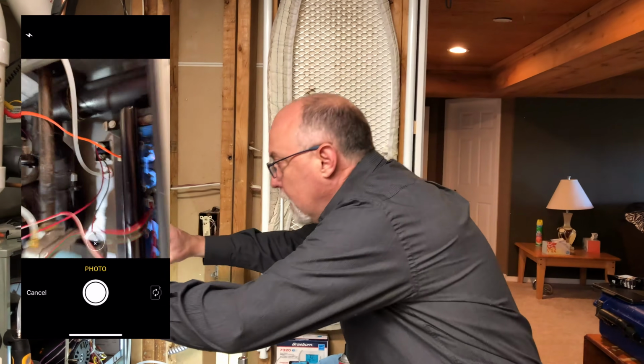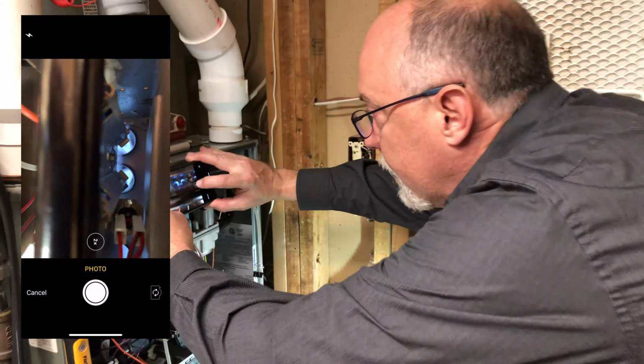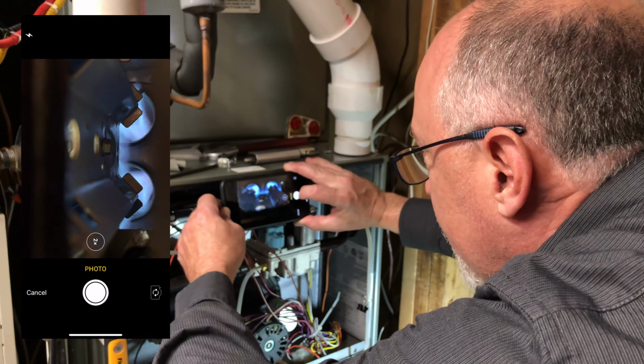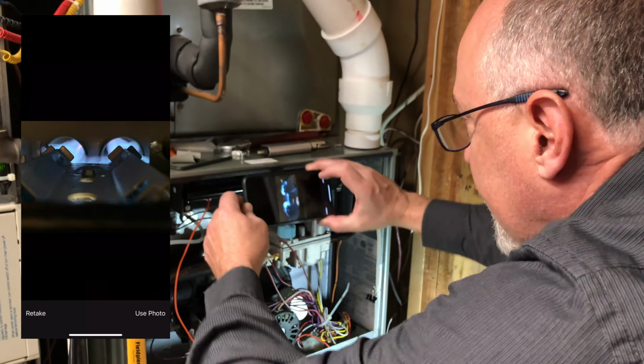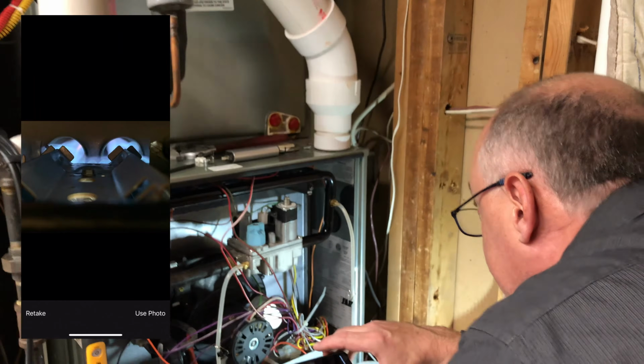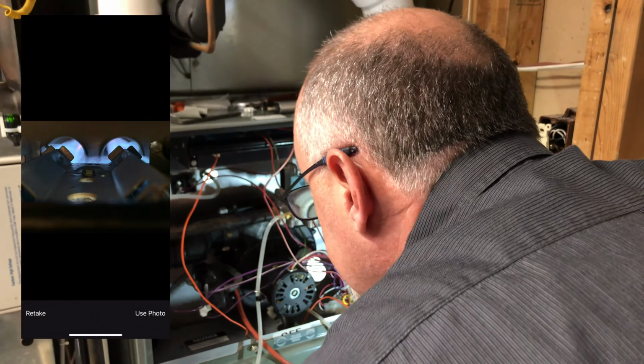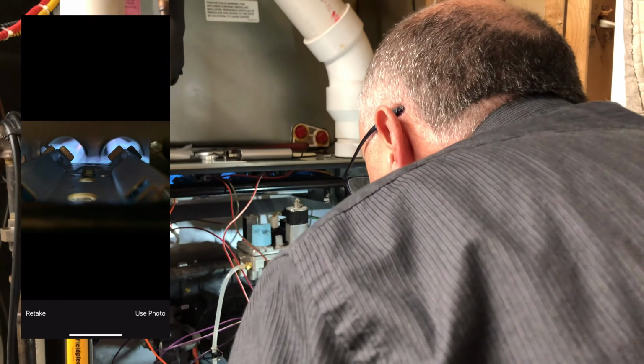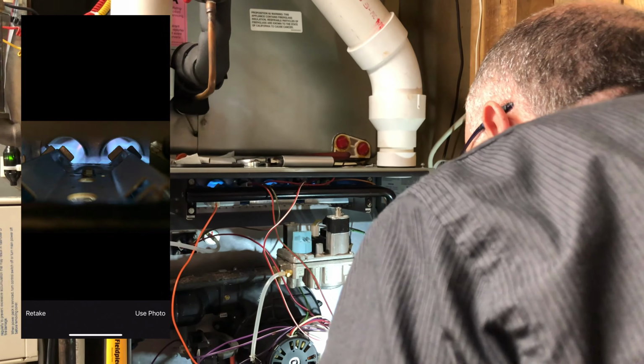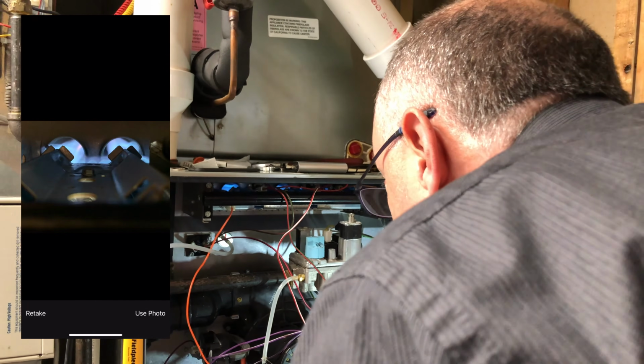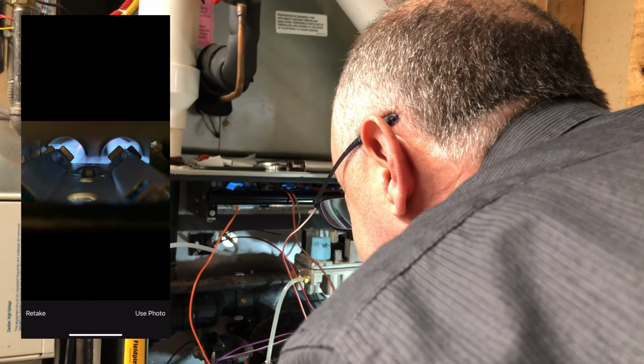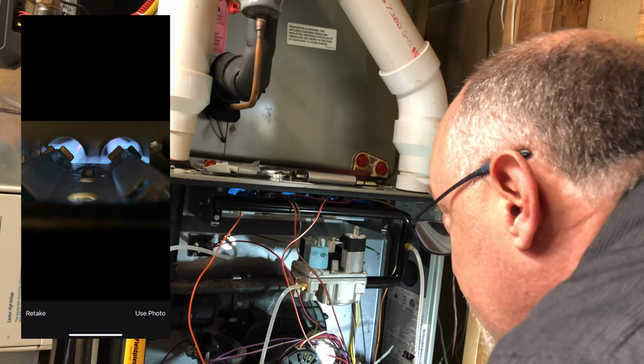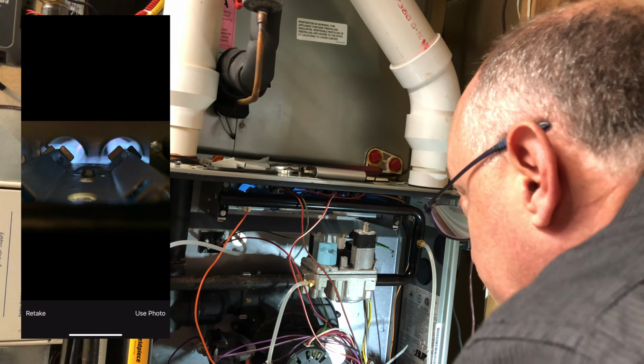Turn the gas on, that always helps. And now I'm just going to zoom in here. I can get a good picture of the flame, and if I look at all these flames, they look really, really nice. It's smooth, and we'll hear the blower kick on in a minute. What we're watching for is any kind of flame disruption indicating a heat exchanger breach in there.